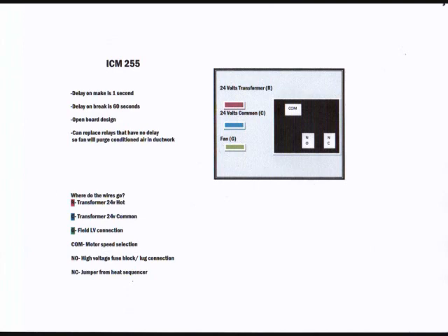This is a layout of what the relay looks like. You can see that there is a delay on make for one second and a delay on break for 60 seconds to purge the ductwork.